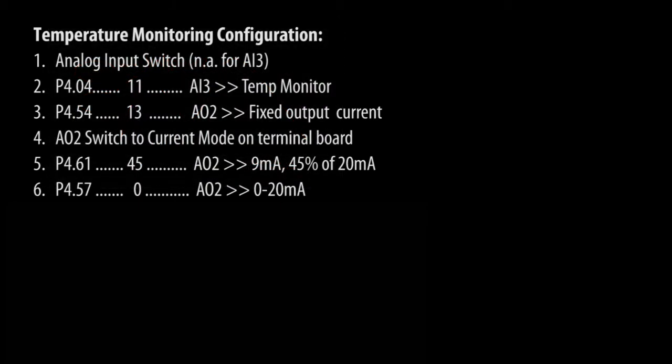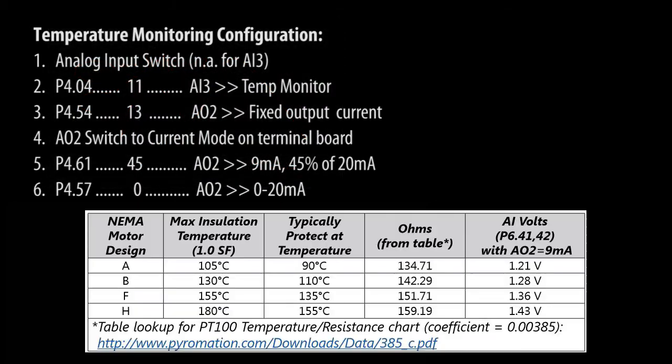We need to tell the GS4 drive the voltages these temperatures generate. If you have a motor with a built-in RTD, then look at the manufacturer's datasheet. That will tell you what temperature you need to watch out for. The example in the GS4 drive's user manual has a chart that will give you some idea what to expect. These motor installation classes will have max temperatures of this. And you'll want to start protecting the motor a good 15 to 20 degrees below that.